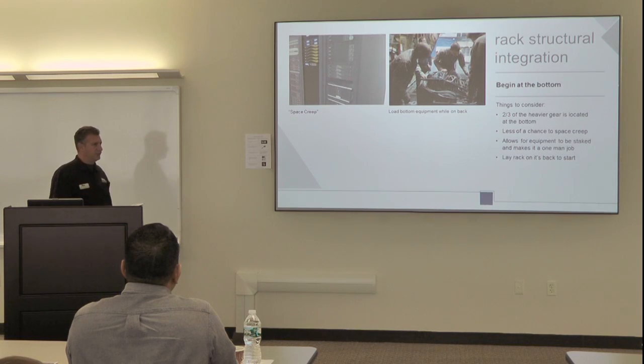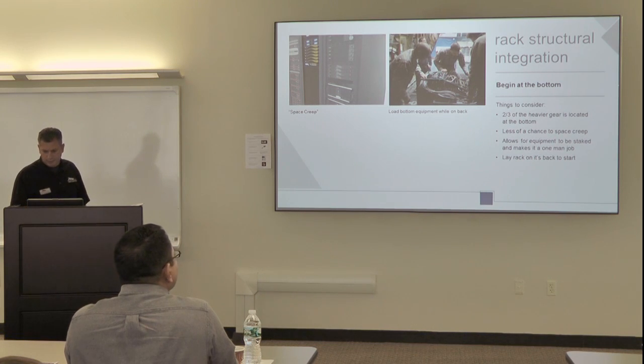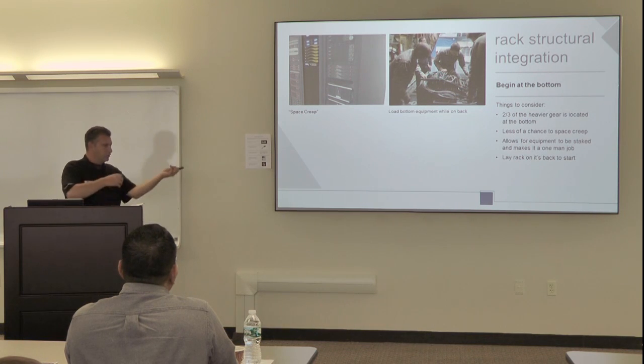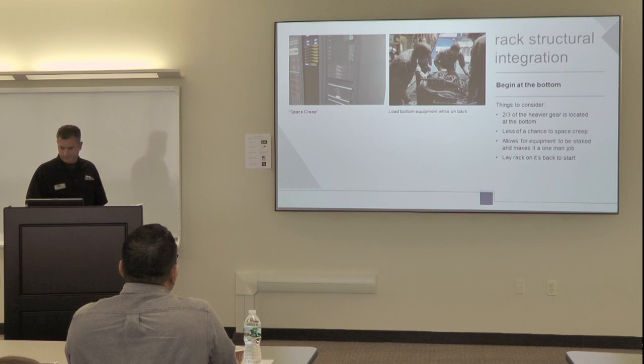That's another benefit of working from the bottom and watching for space creep. Many manufacturers put hash marks and numbers on the rail, so if you see it go past the hash mark, you may run into a problem further up the rack. And again, if you're alone trying to handle a heavy piece, it's easier to drop it in from below than to hold it up.